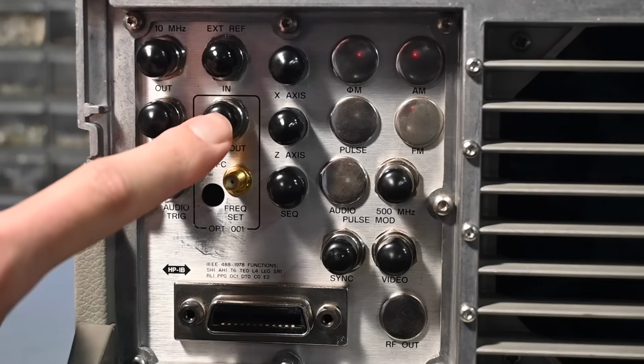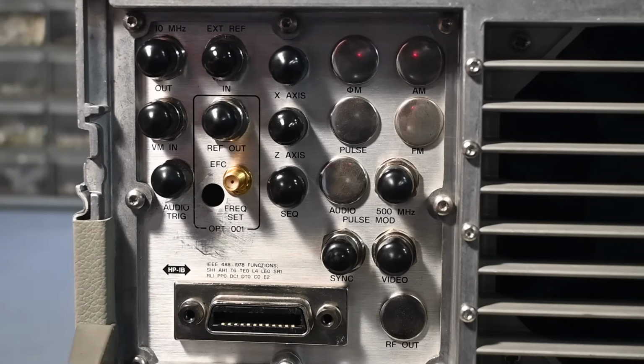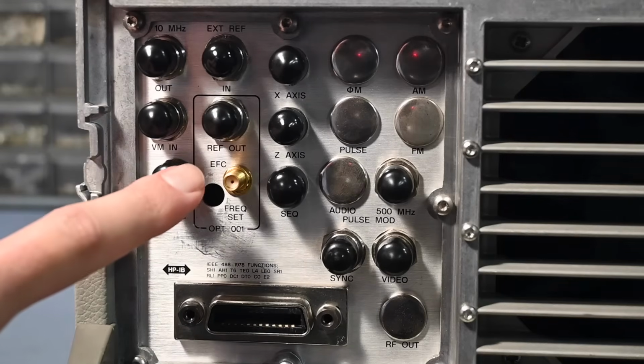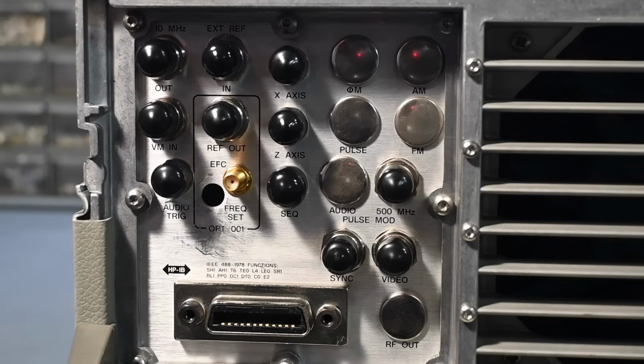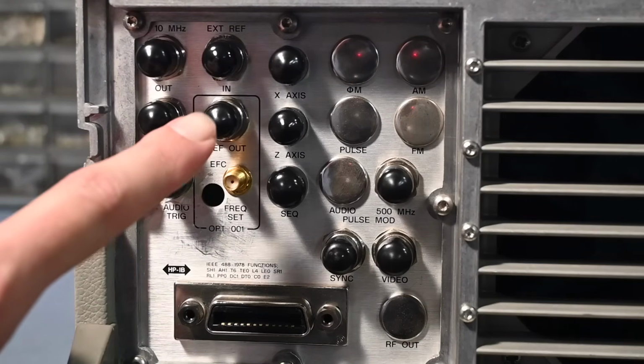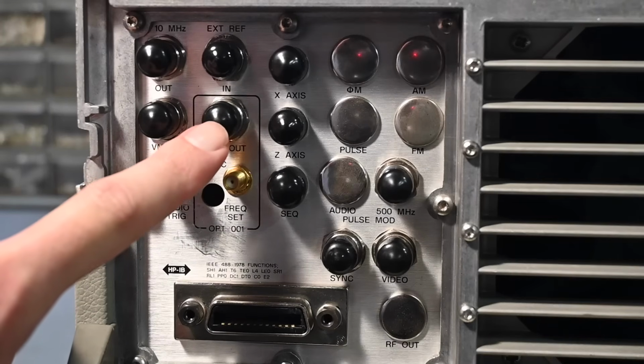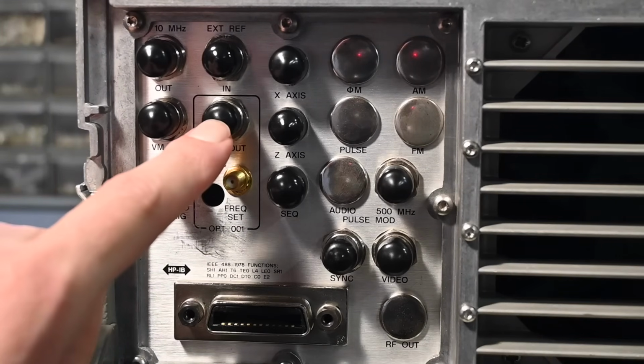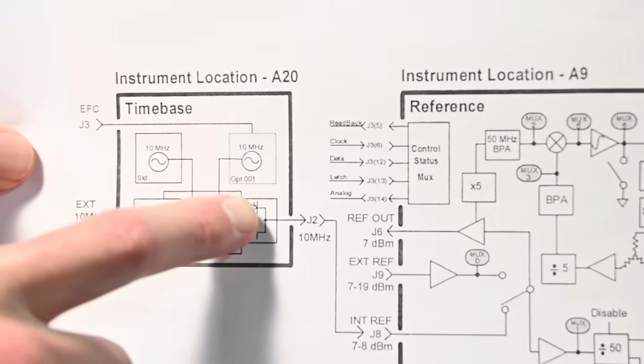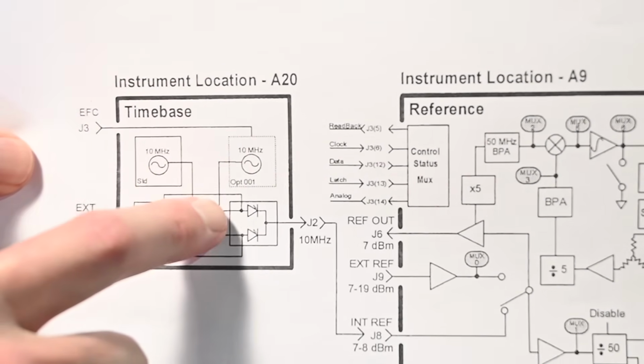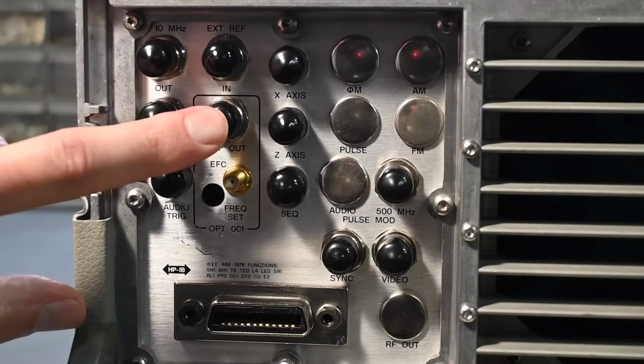So taking a look right here, I did look at the back of the instrument when I first received it, and I saw this connection right here in this blocked in area for the option 1, and my first thought was that this is just a convenience for an output on that reference oscillator that you could use to connect to another piece of equipment, another instrument, maybe to synchronize, so you have the one time base driving multiple instruments. But I'm not really sure that that's what this is for. I think this is the only output of the internal high stability time base. So it's not a duplicate second output, because if we look right here, this option 1 where they show an internal connection right here, I don't think it has that. So I think this is the only output right here.